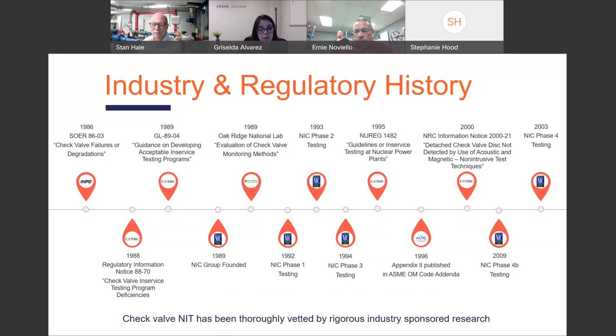We're not in R&D with this stuff. Oak Ridge evaluated check valve monitoring in the late 80s, including acoustics and ultrasonics. The nuclear industry check valve group went through a seemingly endless number of testing projects aimed at verification of the technology. The check valve working group gave us Appendix 2 in 1996. The NRC approved that when they adopted that version of the code in the federal regulations in 1999 without comment or exception. EPRI looked at this just a couple of years ago, and their 2019 report was discussed during the prior session. So after 25 plus years of check valve NIT being allowed in the code, there's been no second-guessing, no pullback from the original positions. This is still the way to go.